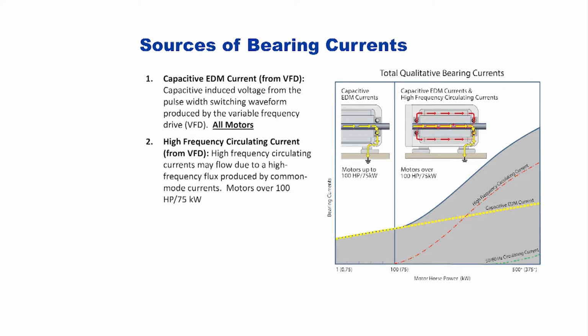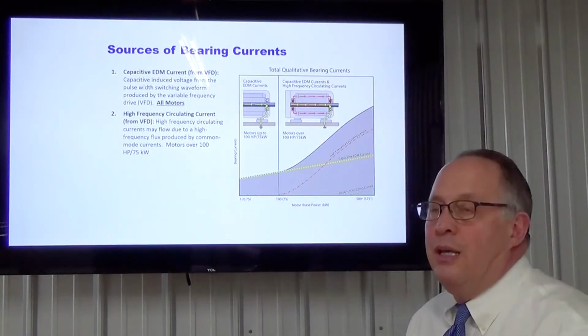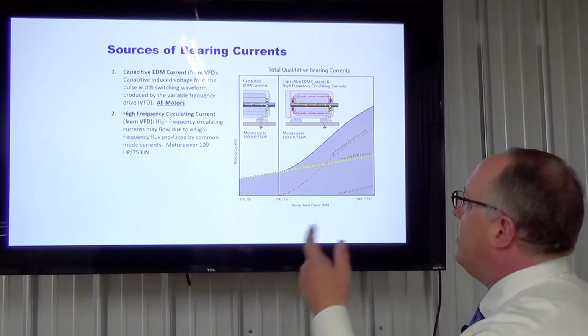Sources of bearing failure. As we discussed before, we got multiple inputs that can cause it, but what actually is happening at the motor itself? Well, we have capacitive EDM current from the VFD. The capacitive induced voltage from pulse width modulating systems will produce an actual voltage onto the drive itself, onto all motors. That's this one up here. Anywhere from, starting at 1 horsepower, fractional horsepower, all the way up to 500 horsepower and above. At higher horsepowers, 100 horsepower and up, we also see the cumulative effect of high-frequency circulating current from the VFD. High-frequency circulating currents may flow due to a high-frequency flux produced in the common mode. That's in larger horsepower motors. Smaller motors, we get the capacitive effects.